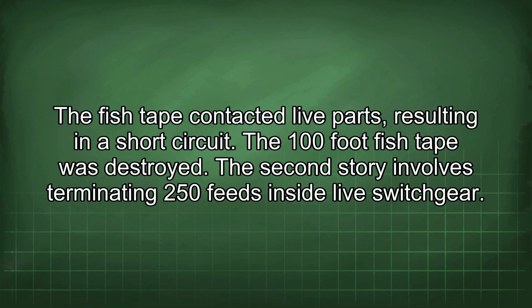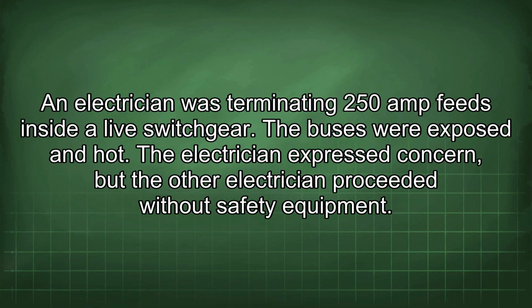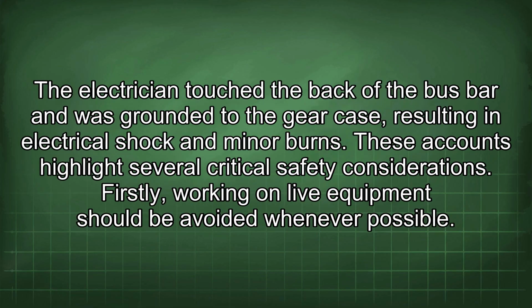The second story involves terminating 250 feeds inside live switchgear. An electrician was terminating 250 amp feeds inside a live switchgear. The buses were exposed and hot. The electrician expressed concern, but the other electrician proceeded without safety equipment. The electrician touched the back of the bus bar and was grounded to the gear case, resulting in electrical shock and minor burns. These accounts highlight several critical safety considerations.